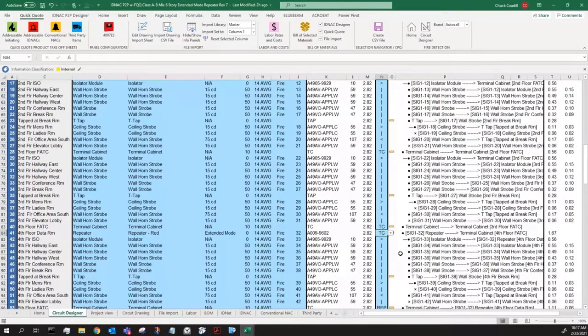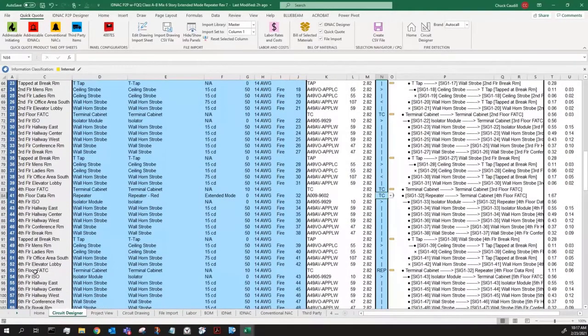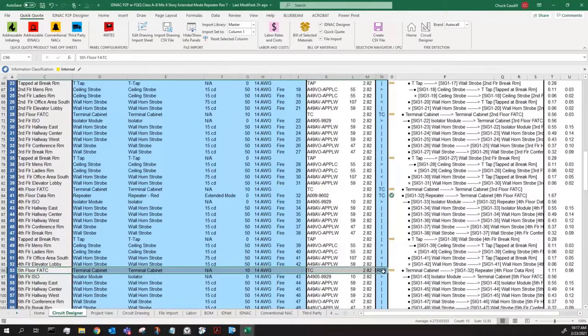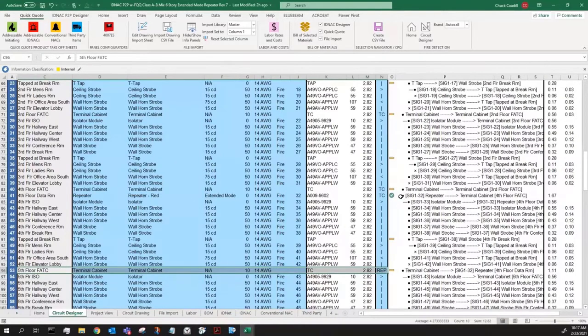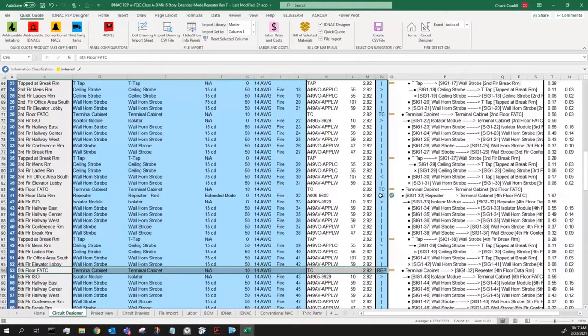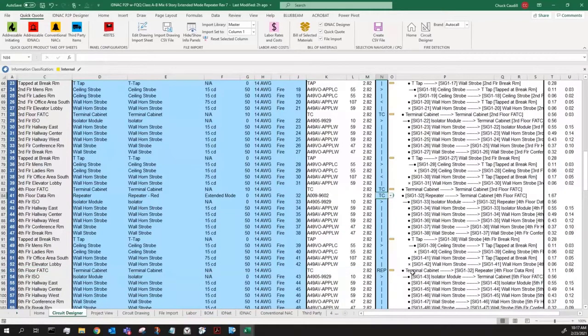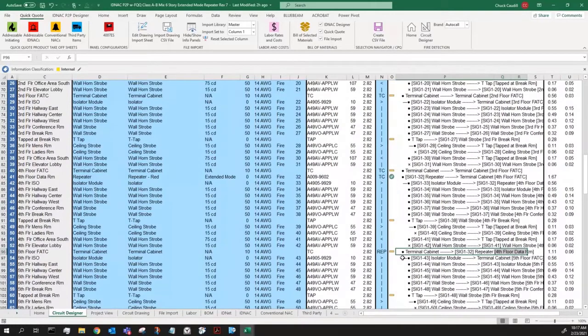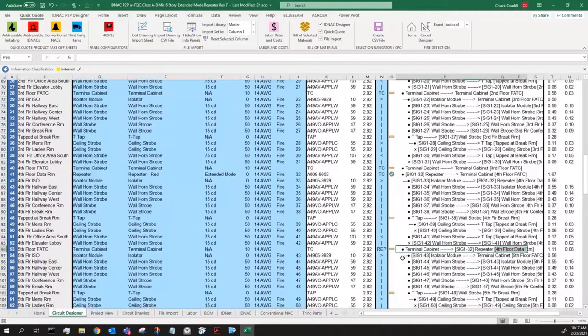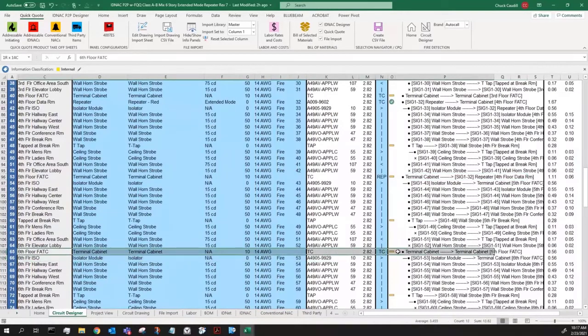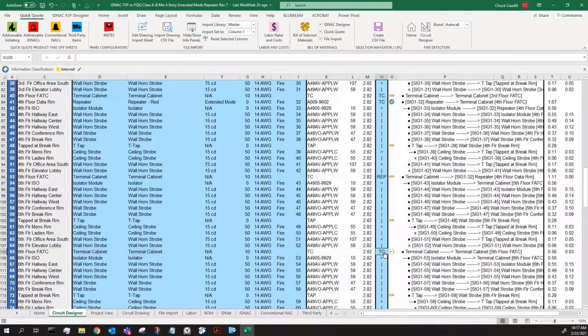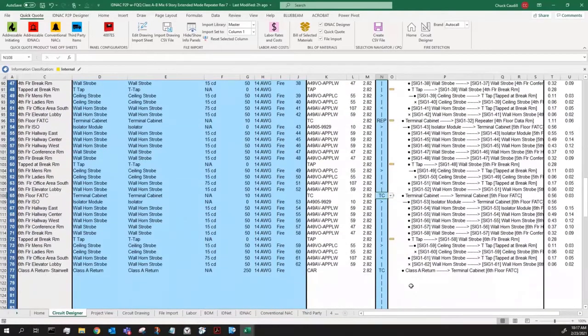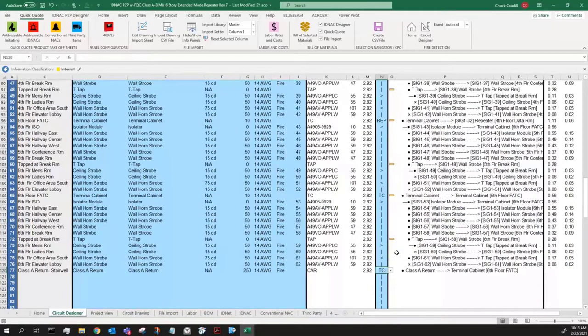When I get up to the next floor, here's the fifth floor FATC terminal cabinet. If I use the TC terminology like I've done on others, what it would do, it would connect this terminal cabinet. It would bypass the repeater, and it would go on the other side to the fourth floor terminal cabinet. I don't want to do that. I want this to be in series with this repeater. So I say scan up the page and put it to the closest repeater, which means here. Terminal cabinet on this floor ties to the repeater in the fourth floor data room. And then when I get up to the sixth floor, I'm back to the same way I was doing it previously. I say tie this to the terminal cabinet above or below, which is the physically below on the next floor down, but above on the page. And then finally, the Class A return ties to the next terminal cabinet.